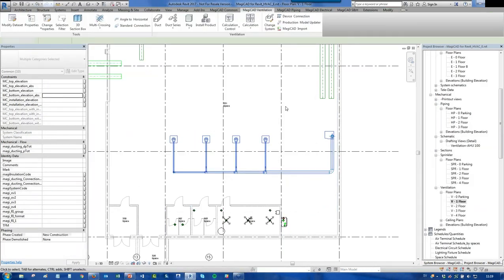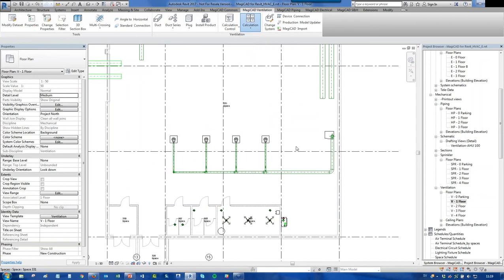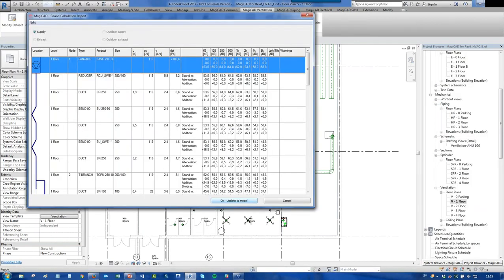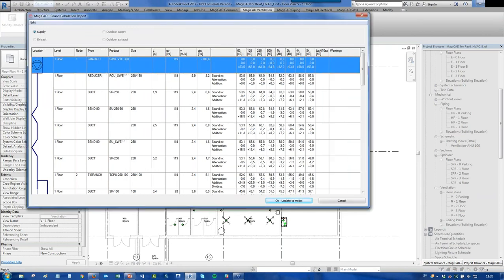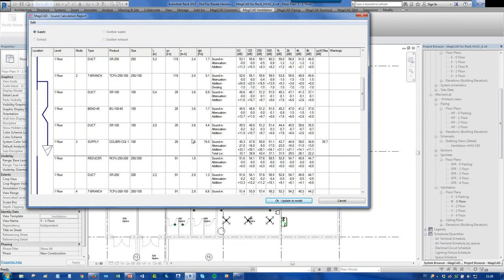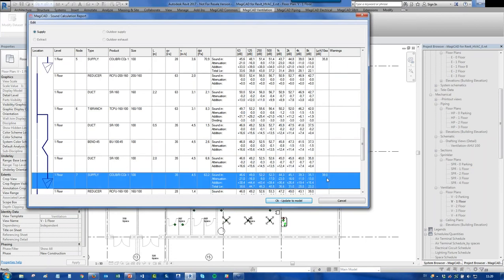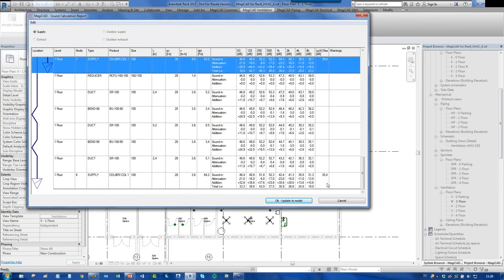If we want to go further, we can also do sound calculation in a similar way, and then calculate and get all the pressure drops for the sound calculation, the fan pressure drop for octave bands, and generation attenuation for each component following that. You can see 35 dB, 39 dB, or whatever it is.